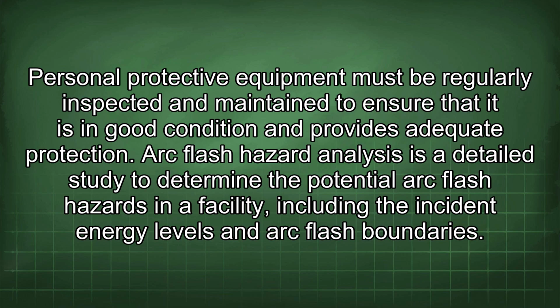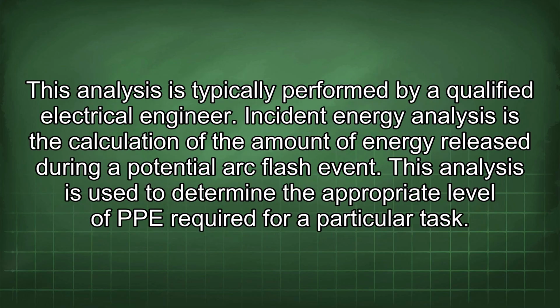Arc flash hazard analysis is a detailed study to determine the potential arc flash hazards in a facility, including the incident energy levels and arc flash boundaries. This analysis is typically performed by a qualified electrical engineer. Incident energy analysis is the calculation of the amount of energy released during a potential arc flash event. This analysis is used to determine the appropriate level of PPE required for a particular task.